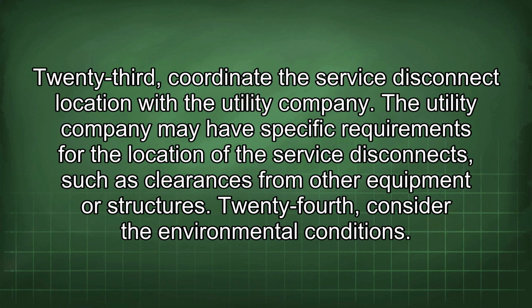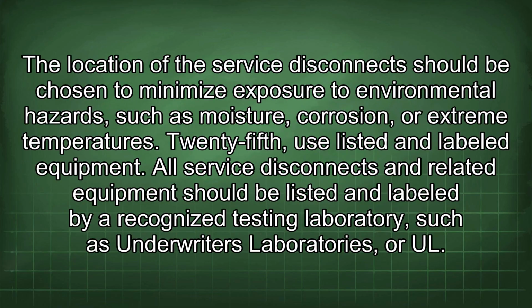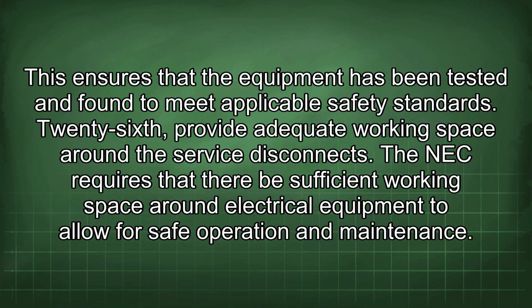23rd, coordinate the service disconnect location with the utility company. The utility company may have specific requirements for the location of the service disconnects, such as clearances from other equipment or structures. 24th, consider the environmental conditions. The location of the service disconnect should be chosen to minimize exposure to environmental hazards such as moisture, corrosion, or extreme temperatures. 25th, use listed and labeled equipment. All service disconnects and related equipment should be listed and labeled by a recognized testing laboratory, such as Underwriters Laboratories, or UL. This ensures that the equipment has been tested and found to meet applicable safety standards.